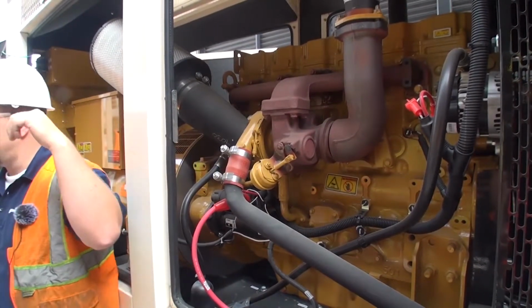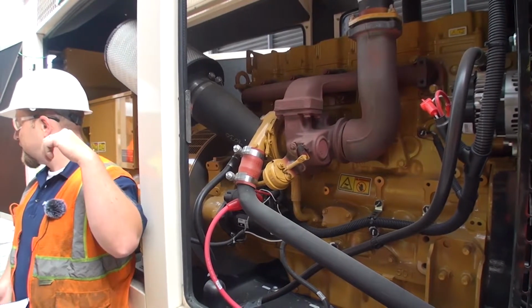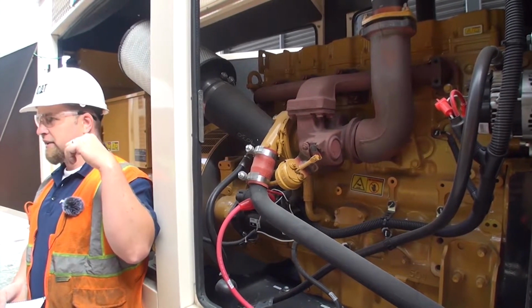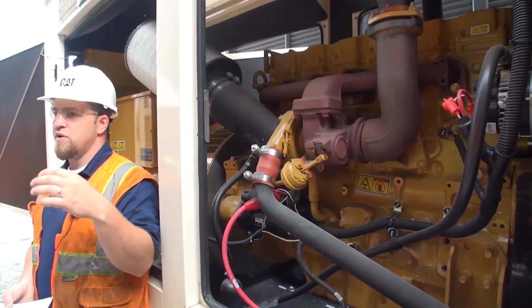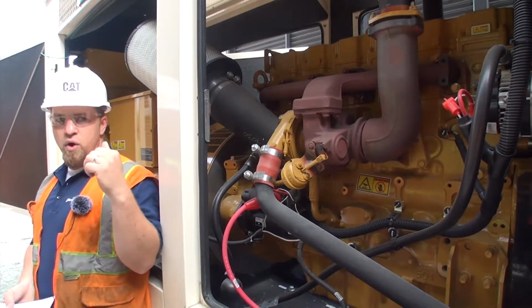You'll start seeing it wet at the bottom and it looks like an oil leak. That's actually what they call wet stacking, and it's from running the unit without enough load all the time, so you start getting oil buildup.